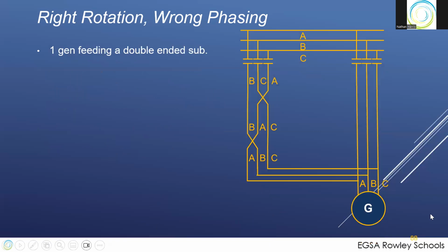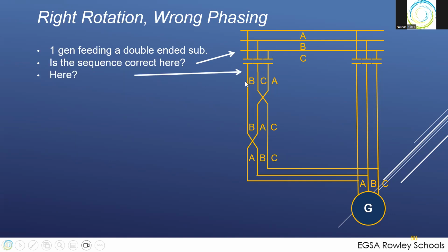Now let's take it one step further. Now we've got 1 gen feeding the double-ended substation. Okay, we routed the wires through different paths to provide our isolation, maybe even 2 breakers off the same gen, providing isolated separate paths in order to accrue some type of backup redundancy. So 1 gen feeding the double-ended sub. Is the sequence correct here? So it's A, B and C. So yes, those are correct. Is the sequence here correct? Well, it's B, C, A, so the sequence is correct.